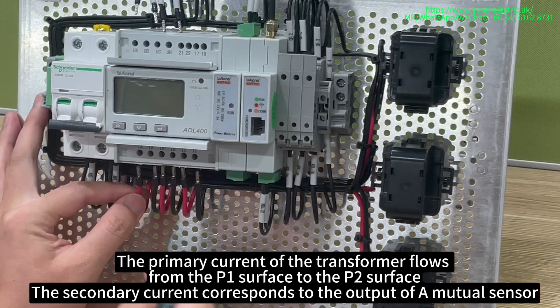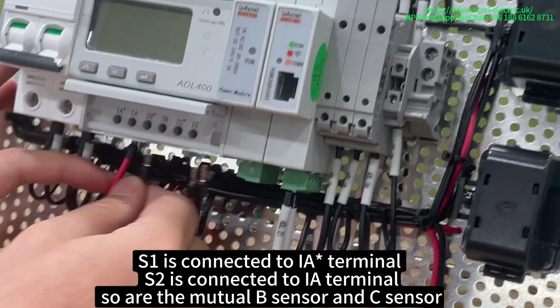In reality, the primary current of the transformer flows from the P1 surface to the P2 surface. The secondary current corresponds to the output of the mutual sensor. For phase A, S1 is connected to the IA* terminal and S2 is connected to the IA terminal. Similarly, for the B mutual sensor, S1 connects to IB* and S2 connects to IB. For the C mutual sensor, S1 connects to IC* and S2 connects to IC.